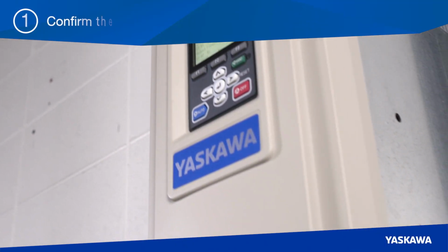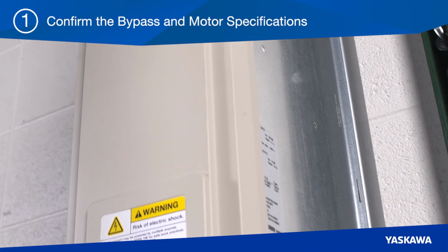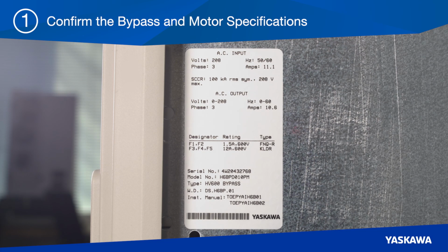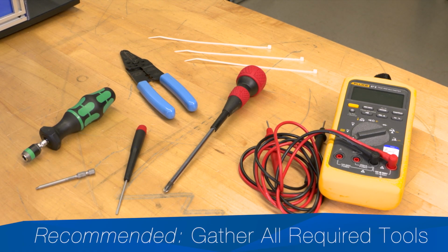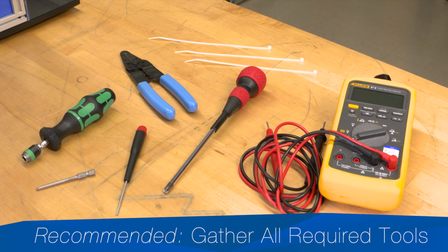The first step is to confirm the bypass and motor specifications. Locate the HV600 bypass nameplate. Nameplate locations may differ slightly between narrow and enclosed bypass models. It's also a good idea to gather all of the tools required so things go smoothly throughout the process.